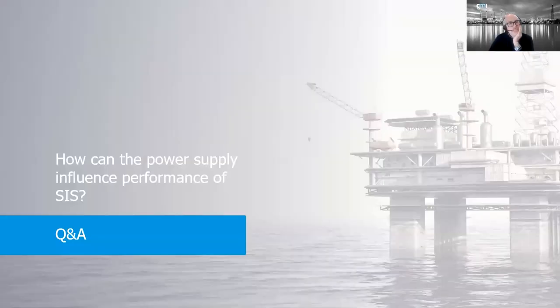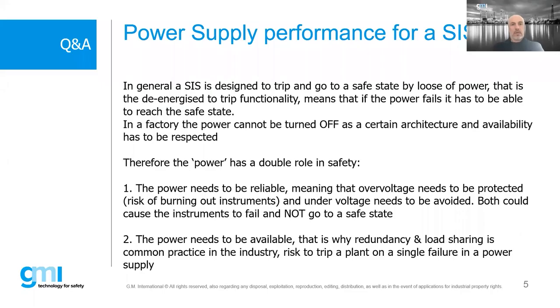Well, Andrea, another question. How can power supplies influence the performance of the SIS and what are the design and preventive maintenance requirements? In this case, of course, the SIS is designed to trip and go to a safe state on loss of power. That is the de-energized condition. So it means that if the power supply fails, it has to be able to reach this safe state. But normally in the factory, as you experience, the power cannot be turned off because there is some architecture, some availability, some process that has to be guaranteed in on condition. So we say that the power has this double role in safety.